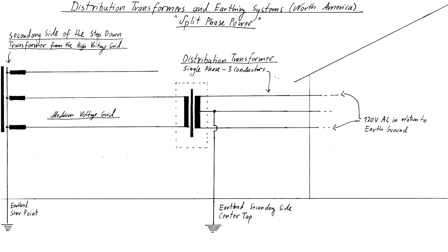Since this is not a polyphase transformer, it of course does not have an earthed star point at the secondary side, but instead it has an earthed center tap, which, like the star point in Germany, makes the supply voltage for the household earth referenced, allowing the use of an RCD.